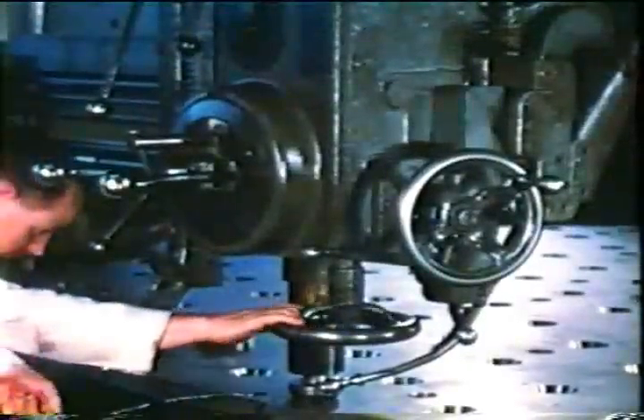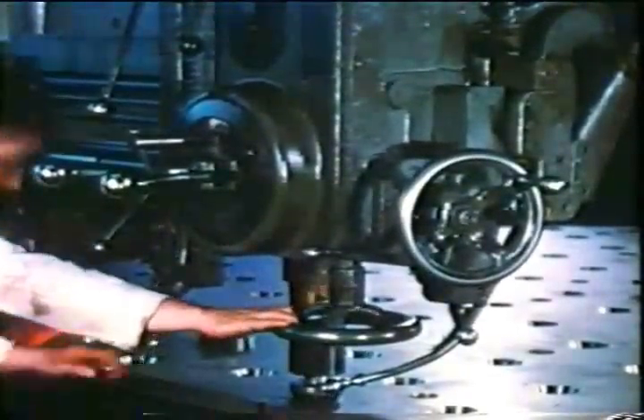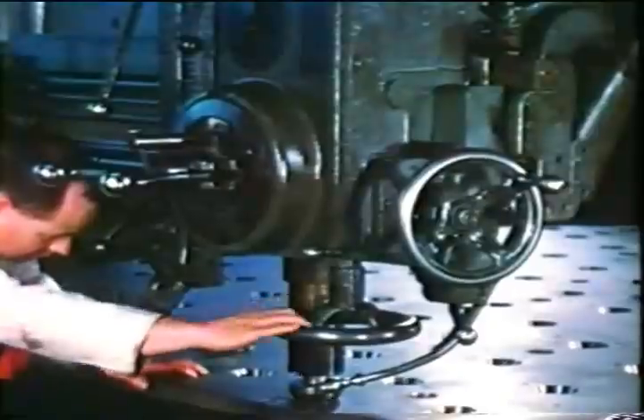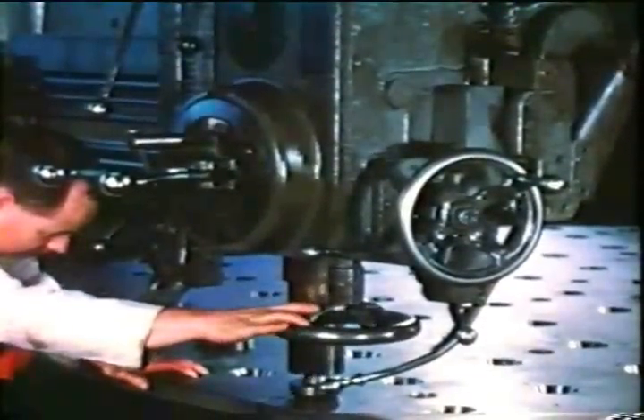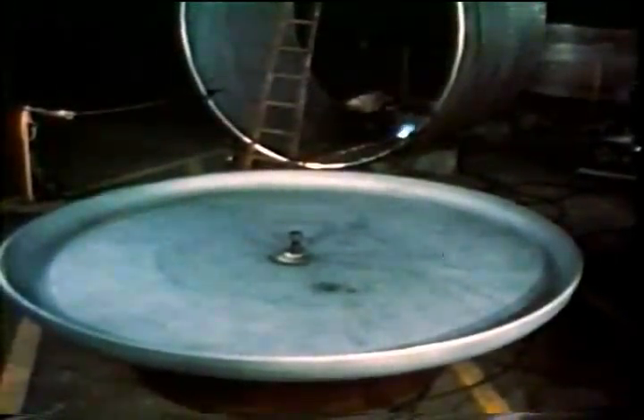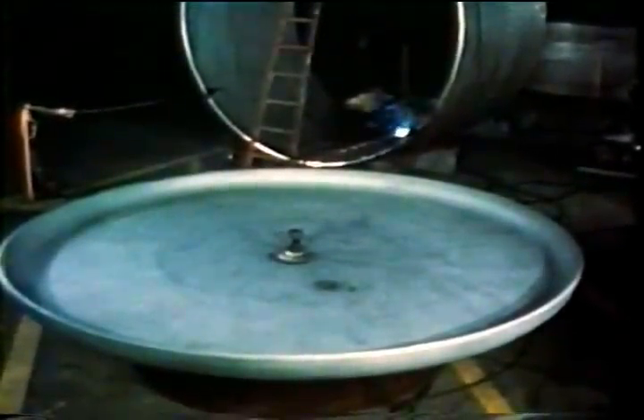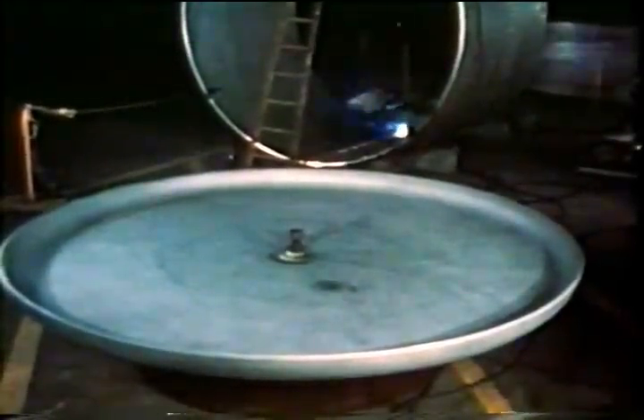A stainless steel grid plate near the bottom of the core tank supports and precisely locates the moderator assemblies. These holes space the lower ends of the moderator cans and fuel elements on an 11-inch triangular lattice. The core is contained within the stainless steel core tank. Its walls are 1.5 inches thick. The bottom head was formed cold and heat treated. The sides of the tank were built of 3 ring sections, each welded in place.